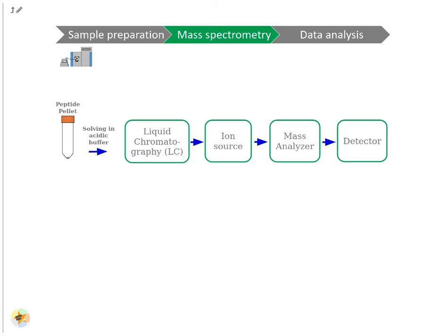Sample measurement in an MS consists of different steps. A high-performance liquid chromatography system is attached in front of the MS, as it separates the injected peptide mixture according to their hydrophobicity. The peptides elute from the LC column into the MS within several minutes to hours. This reduces sample complexity and gives the MS more time for measurement. The acidic LC buffer charges the peptides positively at their N-terminus and the basic lysine or arginine amino acids on the C-terminus. The LC column is directly connected with the ion source needle, where high voltage and heat are applied to evaporate the ionized peptides into the gas phase. This process is called electrospray ionization.